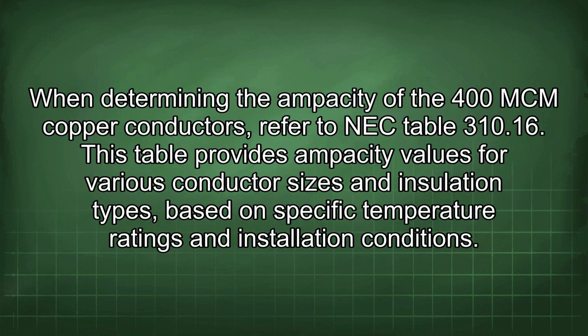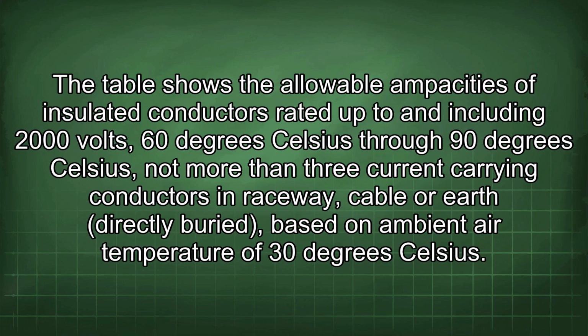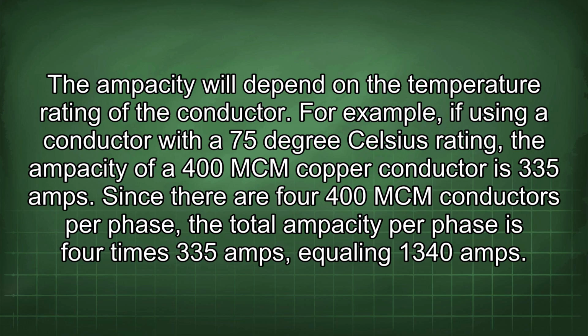When determining the ampacity of the 400 mcm copper conductors, refer to NEC Table 310.16. This table provides ampacity values for various conductor sizes and insulation types, based on specific temperature ratings and installation conditions. The table shows the allowable ampacities of insulated conductors rated up to and including 2000 volts, 60 degrees Celsius through 90 degrees Celsius, not more than 3 current-carrying conductors in raceway, cable or earth directly buried, based on an ambient air temperature of 30 degrees Celsius. The ampacity will depend on the temperature rating of the conductor. For example, if using a conductor with a 75 degrees Celsius rating, the ampacity of a 400 mcm copper conductor is 335 amps.